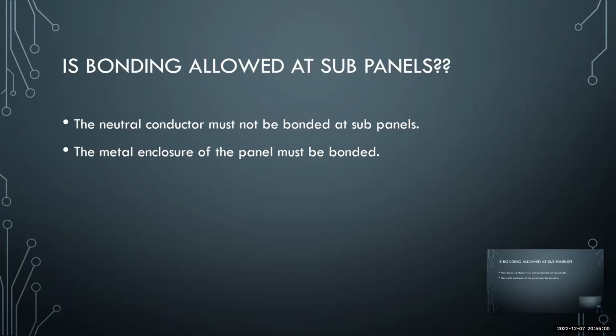Good point. Okay, is bonding allowed at sub panels? This gets discussed a lot and is a confusing point with a lot of inspectors. I hear some discussion sometimes where home inspectors say, you do not bond a sub panel. Well, that's an incomplete statement. All metal enclosures have to be bonded. And if it's a metal sub panel, that sub panel has to be bonded. But the neutral does not get bonded in the sub panel.